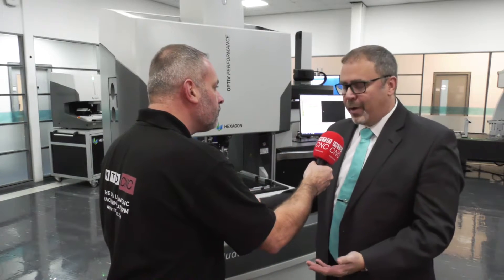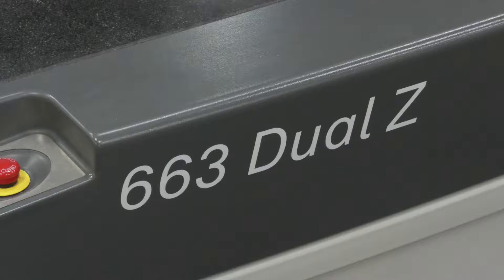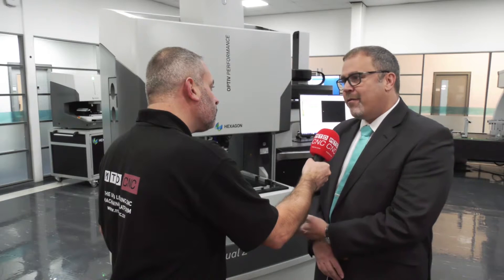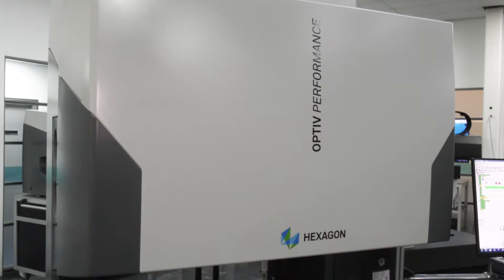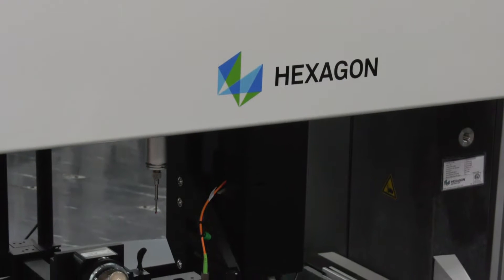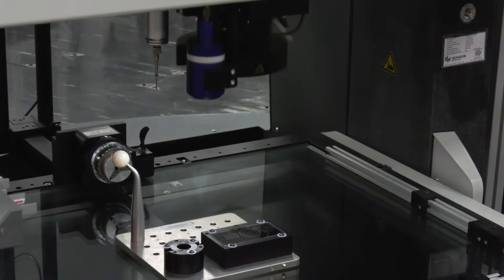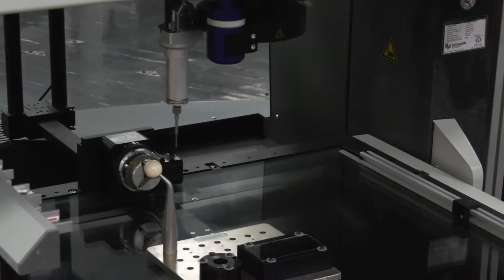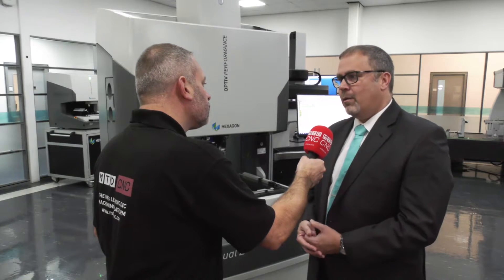The product line is called Optiv — we've got a range of 11 machines in the family. This one is just above the middle size. It has a unique feature that is purely a Hexagon product, which is the dual Z system. On this machine we've got independent Z-axis for the camera or optical system sensors, but also the tactile sensors as well, so we can mitigate collision risks and also speed up the cycle time when running a program.